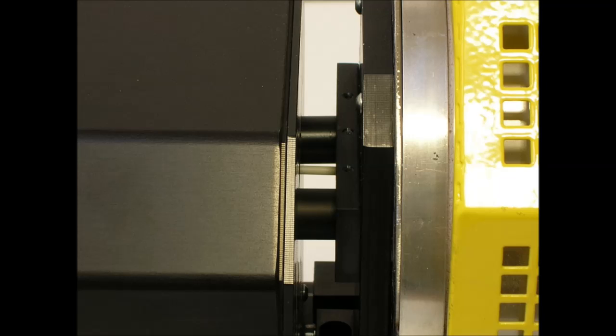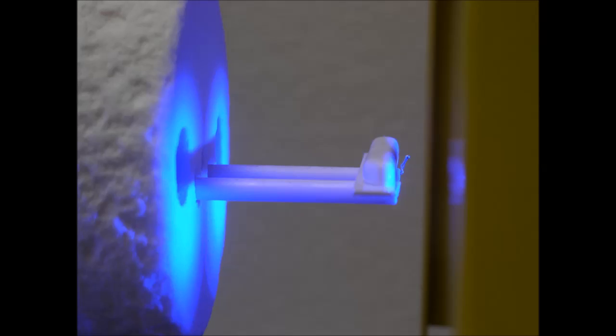The two optical paths are completely protected, and all the optical setup is enclosed inside of a body which is moved by a micrometric control to enable a very precise focusing. The sample is 50 mm long, and it can be pressed from powder or cut from the material to be analyzed. The sample is held in place by two refractory rods, and it can be supported by an alumina plate. The sample is placed horizontally on the alumina plate, or directly on the two rods.